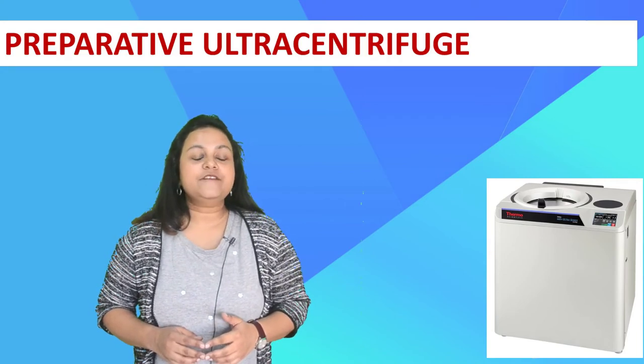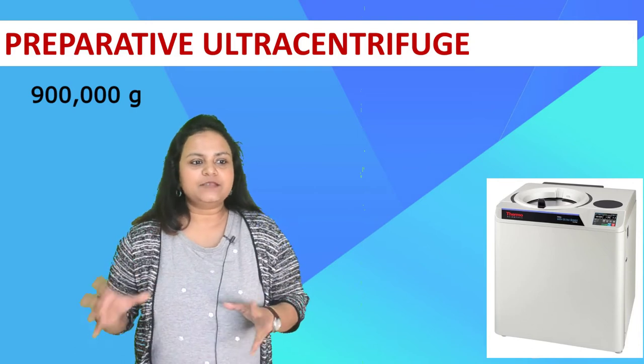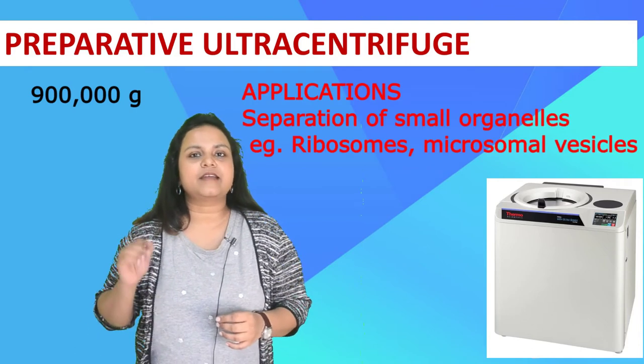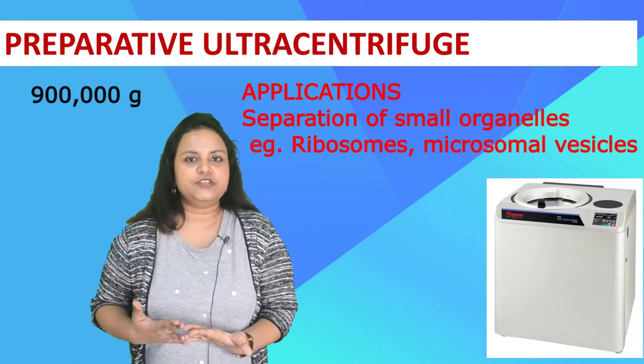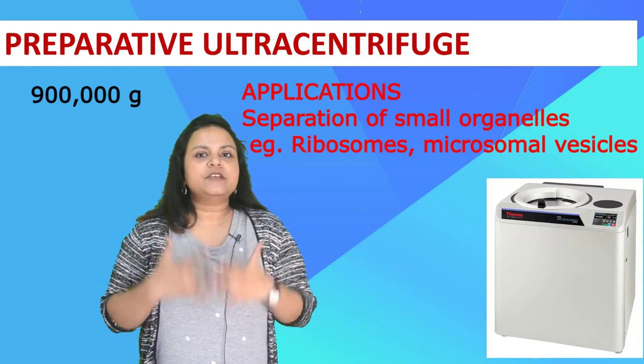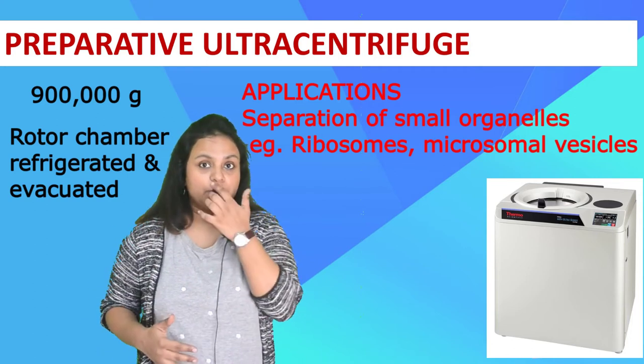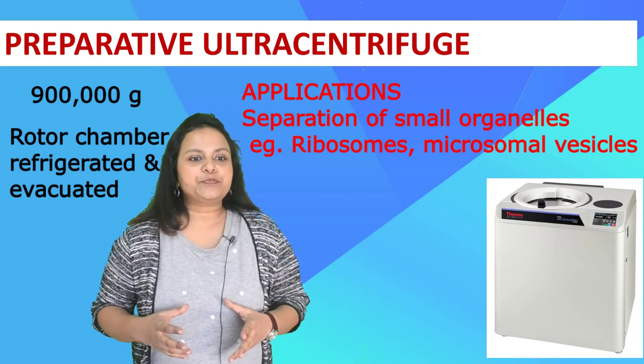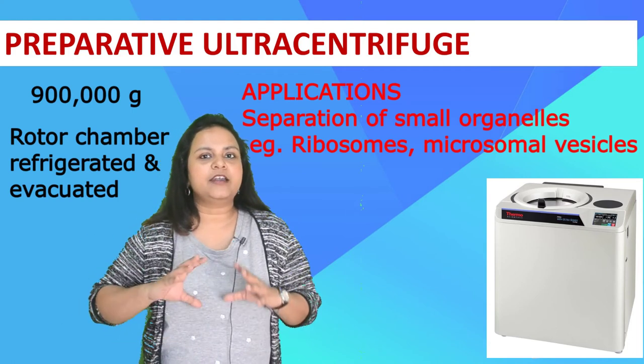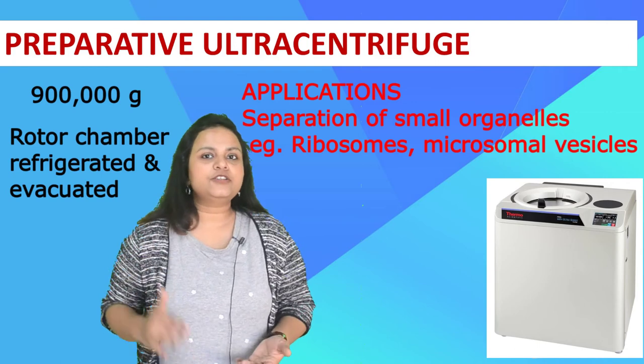The fourth centrifuge is the preparative ultracentrifuge, which operates at even higher velocities than the high speed centrifuge — up to 900,000 G. This speed is useful for even smaller organelles like ribosomes and microsomal vesicles. Operating at such speeds creates a lot of frictional resistance and heat, so the rotor chamber is almost always evacuated and refrigerated before the centrifugal run, ideally about an hour prior. Operating this centrifuge requires careful planning — you must switch it on, create a vacuum in the rotor chamber, load your samples, and bring the temperature down before you can run it.